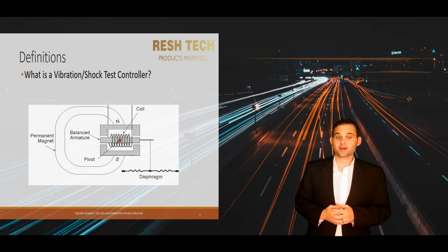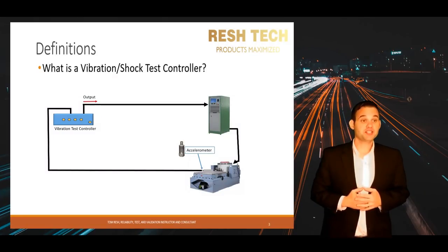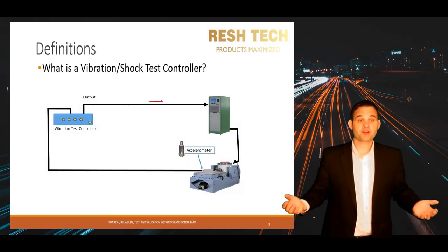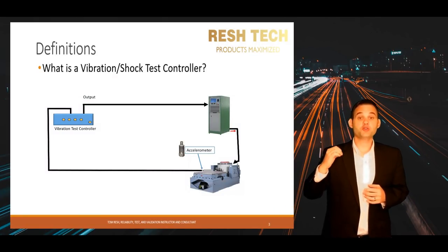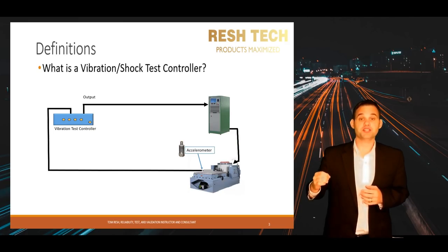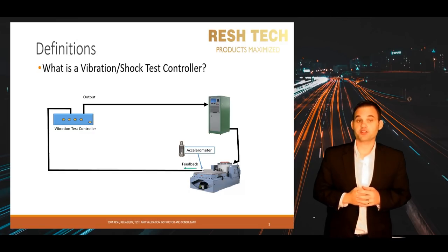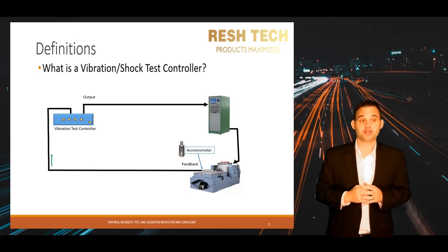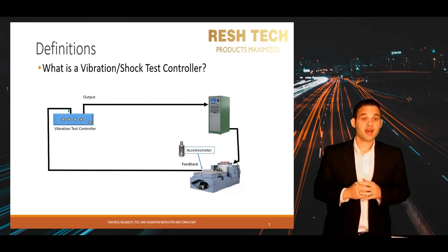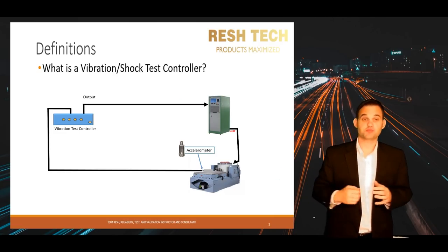The accelerometer can be thought of as your ears and senses the music. The test controller uses a closed-loop strategy that uses feedback to make adjustments to the output signal from the vibration test controller to the amplifier, and ultimately converts it to mechanical energy and movement on the vibration test system. In other words, a closed-loop system uses feedback to make adjustments to the output signal.